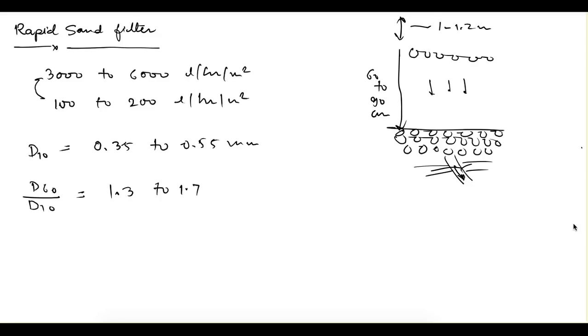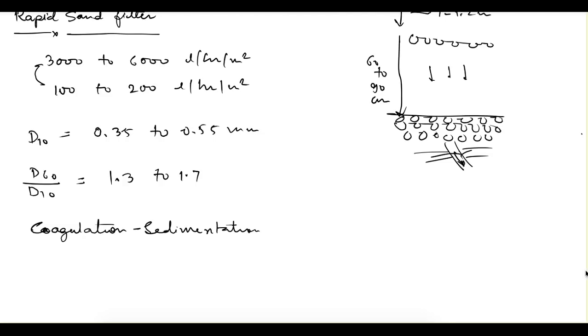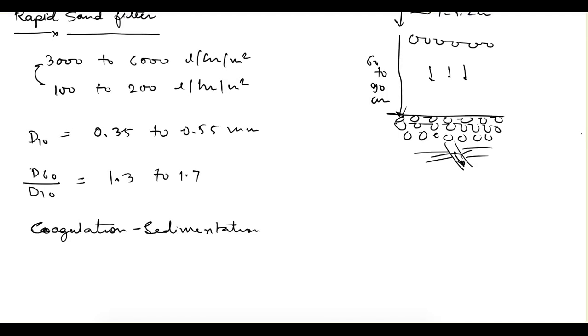In this treatment process, water is applied from the coagulation sedimentation tank. The water is first sedimented with the help of a coagulant, and then it is used in the rapid sand filter. So even if some turbidity remains in the water, it is already removed in the coagulation sedimentation tank. The typical filter area used here is between 10 to 80 meter square for one unit, whereas in a slow sand filter this filter area is between 100 to 2000 meter square.